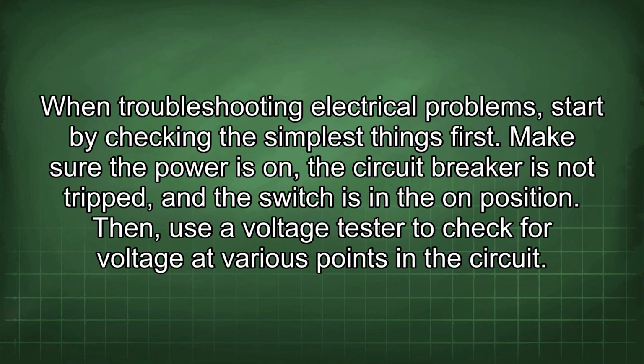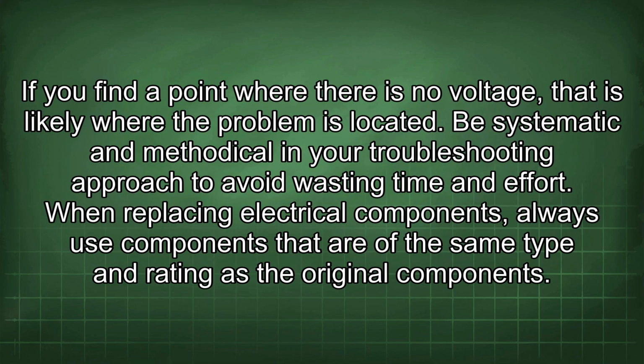When troubleshooting electrical problems, start by checking the simplest things first. Make sure the power is on, the circuit breaker is not tripped, and the switch is in the on position. Then use a voltage tester to check for voltage at various points in the circuit. If you find a point where there is no voltage, that is likely where the problem is located. Be systematic and methodical in your troubleshooting approach to avoid wasting time and effort.